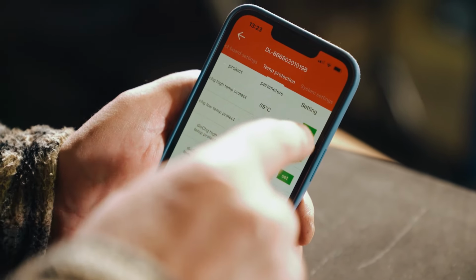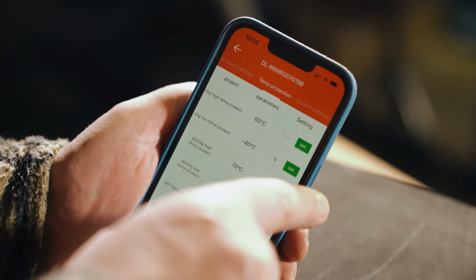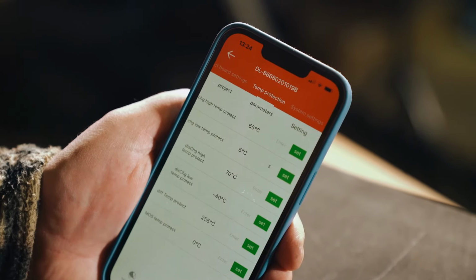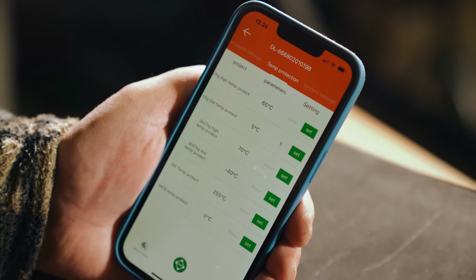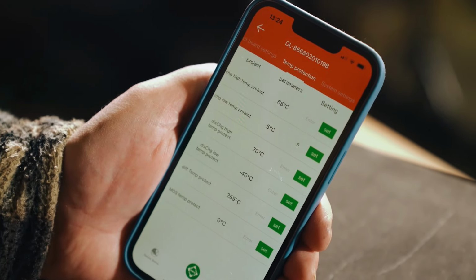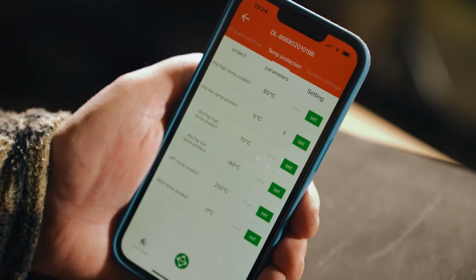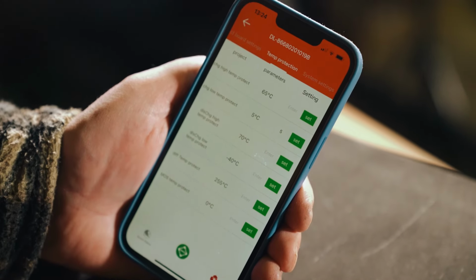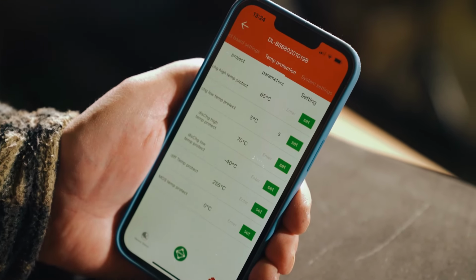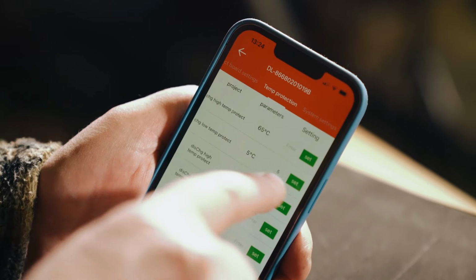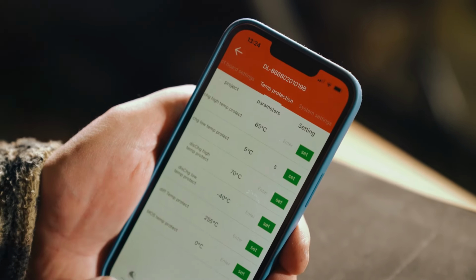Some folk change it back down to 3 or so, but don't ever go less than about 2, because even though you shouldn't charge below 0 degrees centigrade, you shouldn't give it a high charge between sort of 2 and 3 degrees centigrade either. So that's changed to 5. Those are the settings we use.